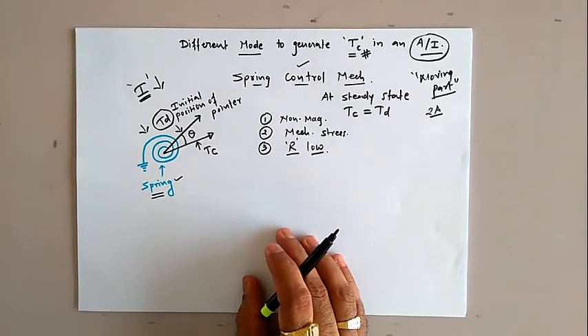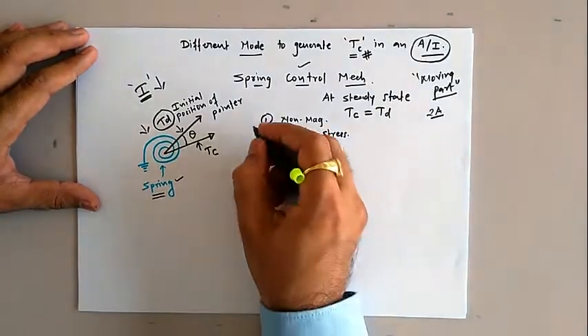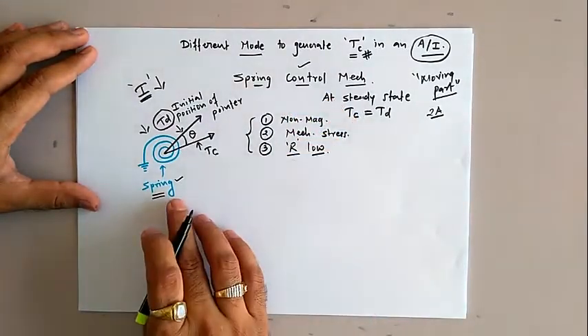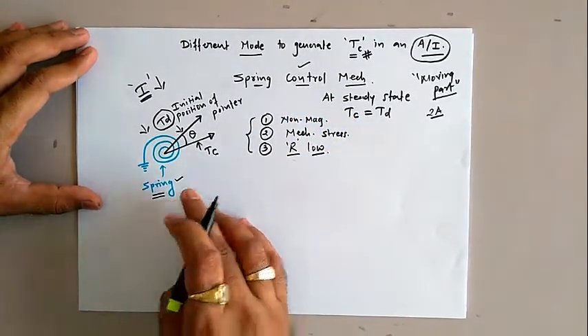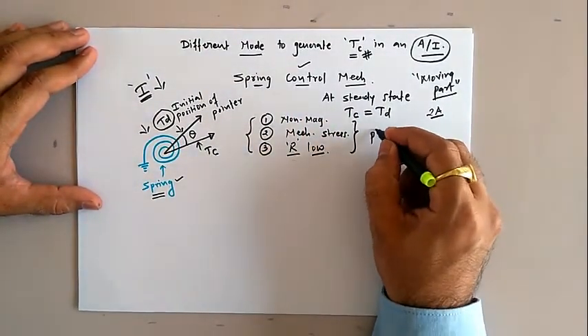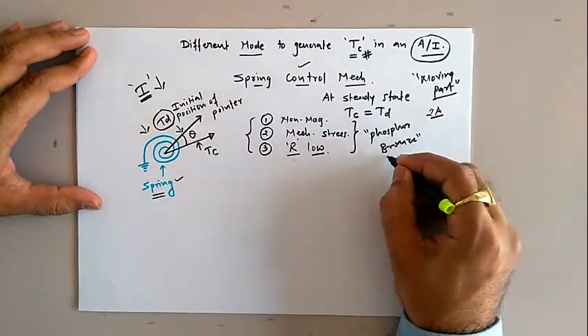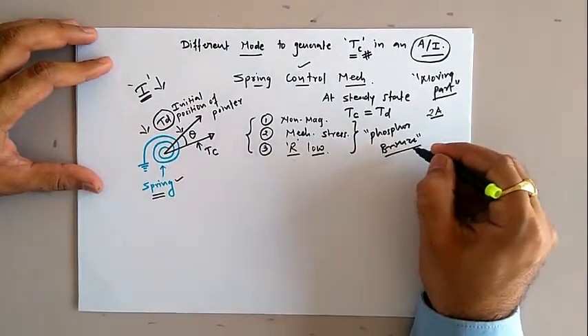To overcome that problem, we need to select materials that offer very low resistance to the flow of current. These three properties — non-magnetic nature, freedom from mechanical fatigue, and low resistance — are available in phosphor bronze material, and that is the reason the spring is made of phosphor bronze in most cases.